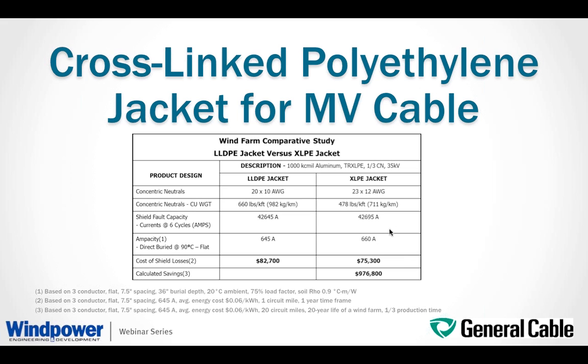And then here, based on 20 circuit miles of cable over a 20-year life of the wind farm, they are estimating the cost of the losses in the cable, so the operating expense, and comparing again side by side what the calculated saving would be over a 20-year span.